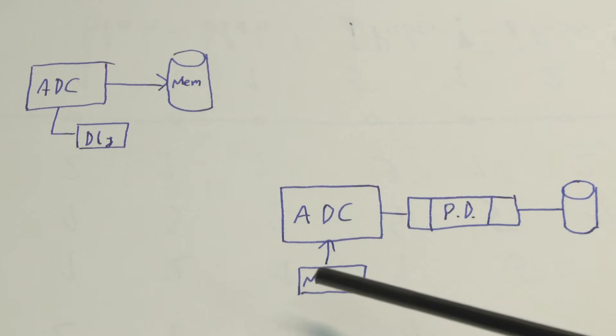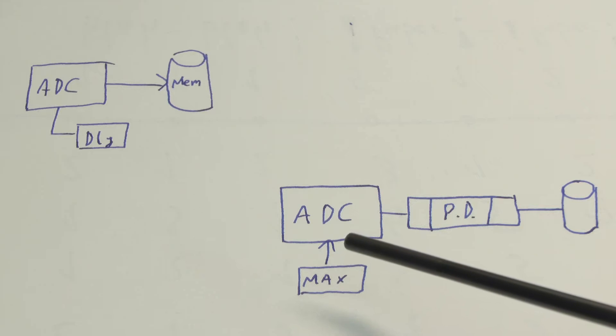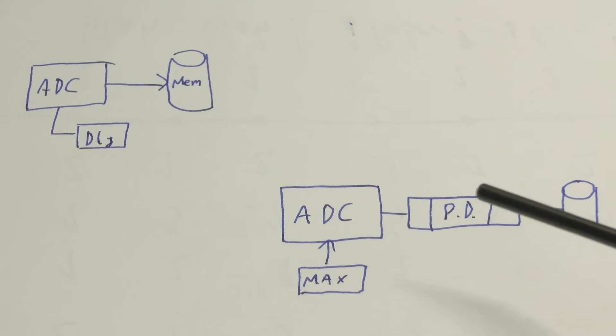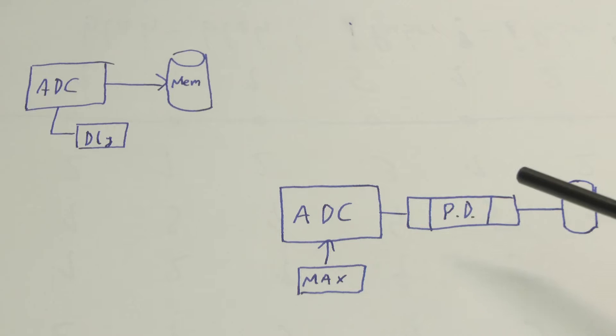Peak detect solves it in a more intelligent fashion. Namely, the ADC is always running at its maximum sampling frequency and the data is being reduced in an intelligent process, namely called peak detect. And how this peak detect process works, we are now going to see in an example frame.